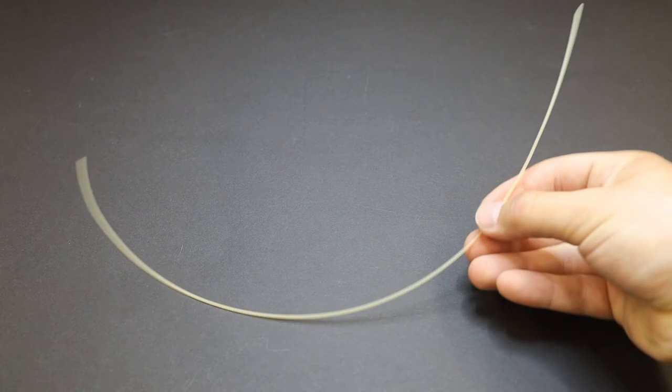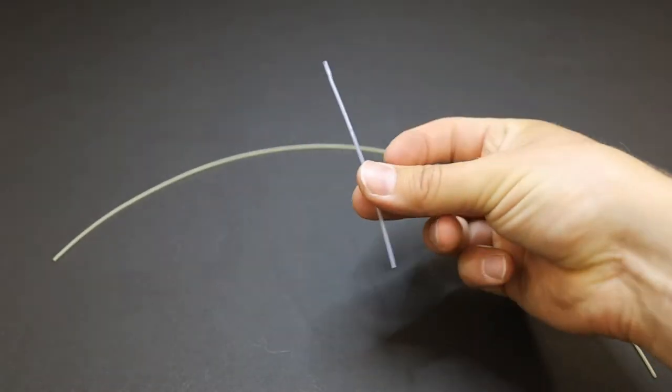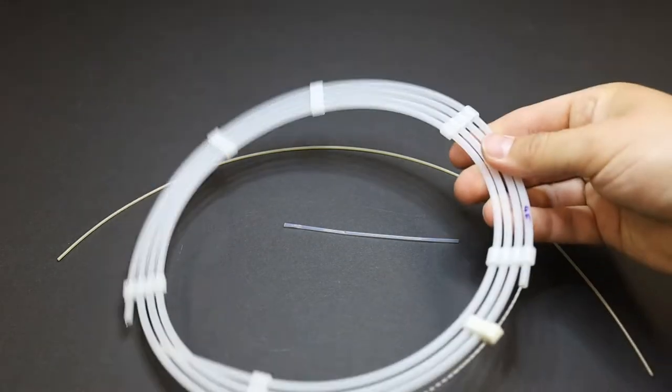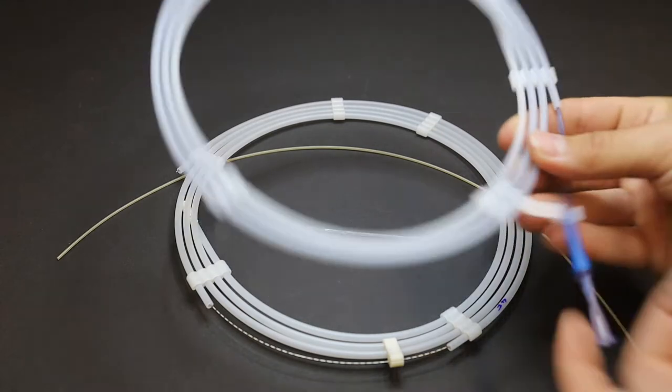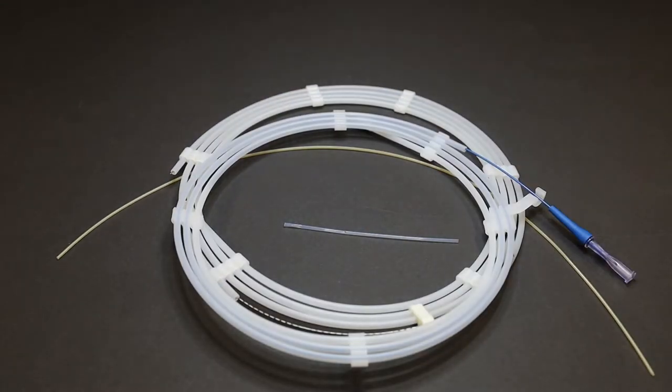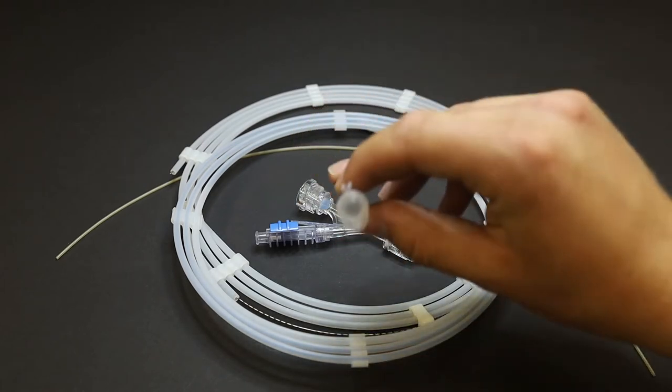To load the microcatheter with the implant, we need several things. An introducer into which the implant is placed, an additional tube which simplifies the insertion, a transport wire, the microcatheter, a Y connector valve for flushing, and of course our implant.